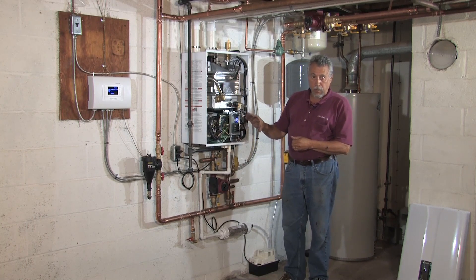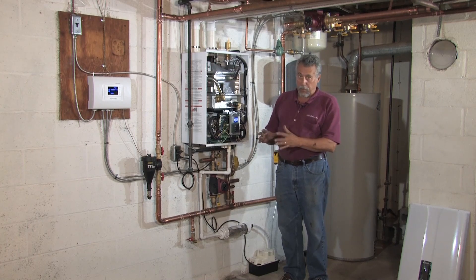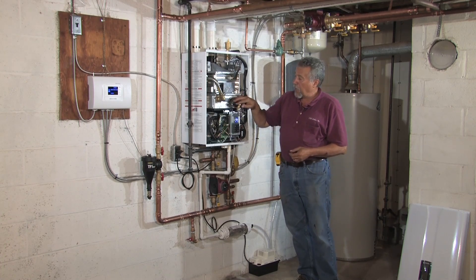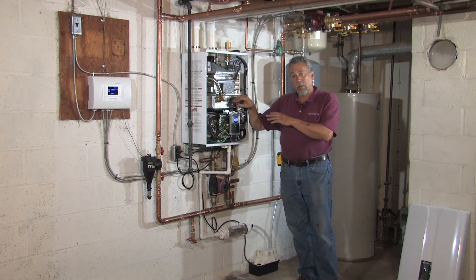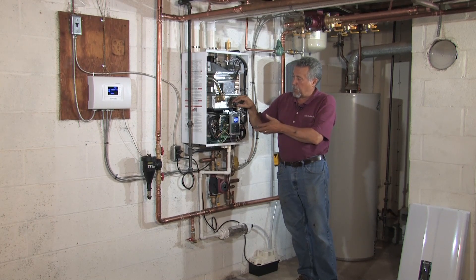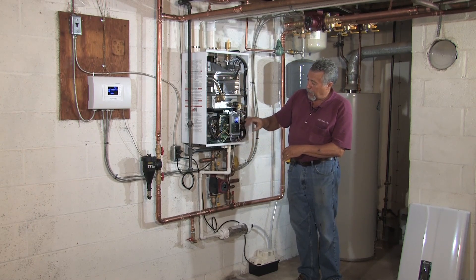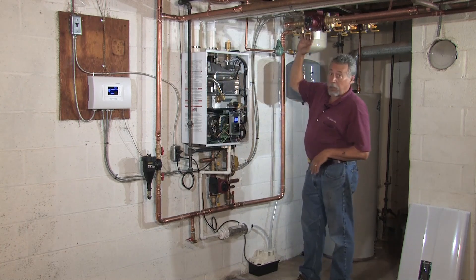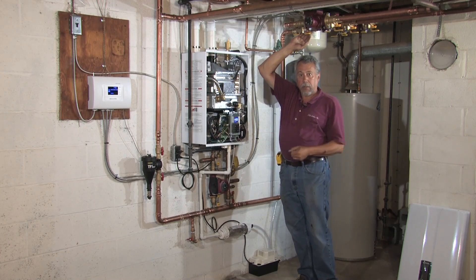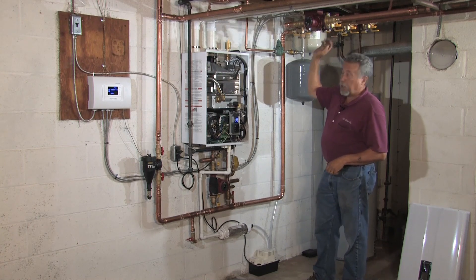The NHB also has a priority control. If you're using an indirect water heater, you can set that up for priority with a timeout for whatever period you program. Part of today's code compliance deals with maintaining adequate pressure inside the boiler — this doubles as a low water cutoff and is adjustable, so you can set the boiler for a minimum of four pounds. If it drops below that, it'll shut down. There's no separate pressure gauge — the pressure is registered digitally right here. When we were purging to get the air out of the system, I was able to watch the digital pressure gauge ramp up, compress the air upstairs, blast that open, and get rid of it. Since we're pumping away from the expansion tank, we don't expect to ever be back here to bleed air again.